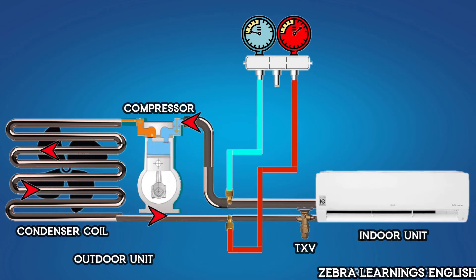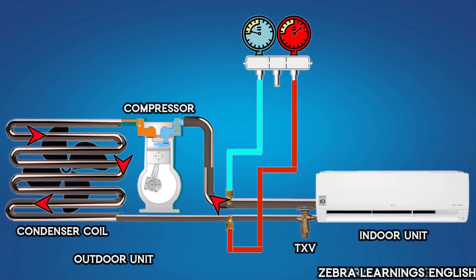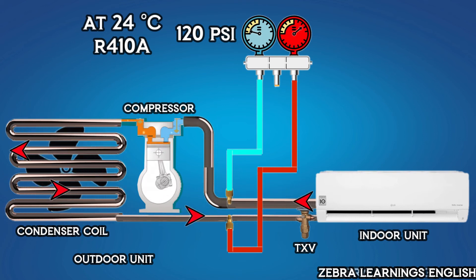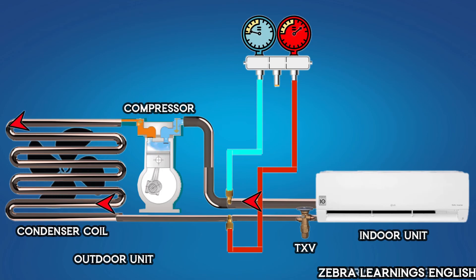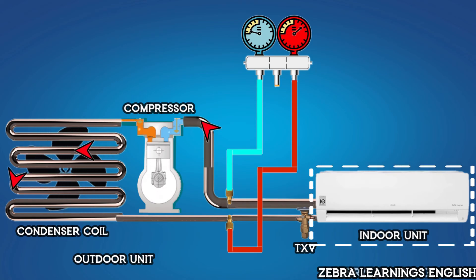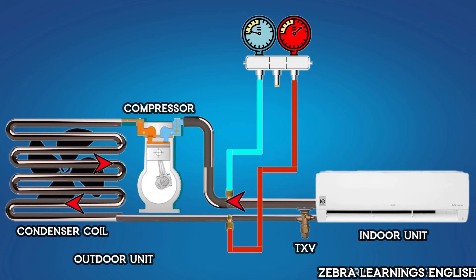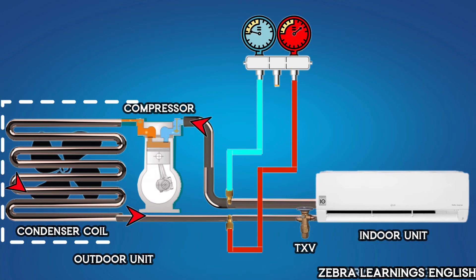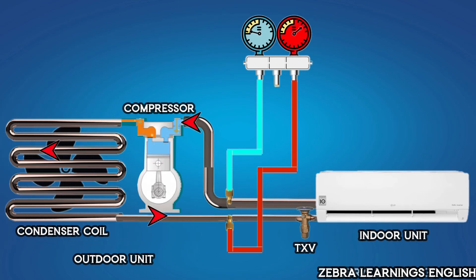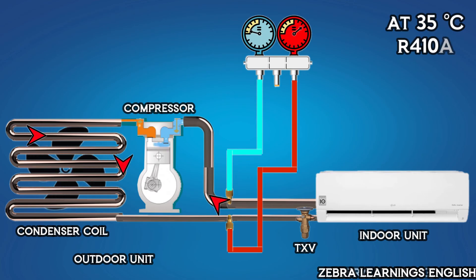When the unit is running, the refrigerant pressure in the suction line is 120 PSI at 24 degrees Celsius. The refrigerant pressure in the suction line comes from the evaporator in the indoor unit. The refrigerant in the discharge line comes from the condenser in the outdoor unit. Refrigerant pressure in the discharge line can be up to 600 PSI at 35 degrees Celsius.